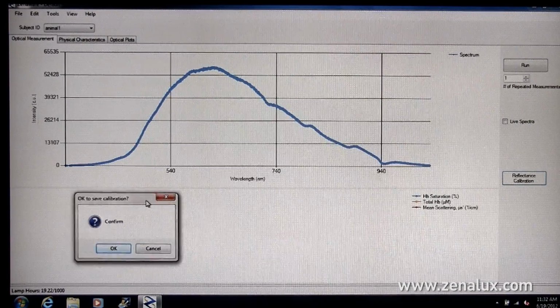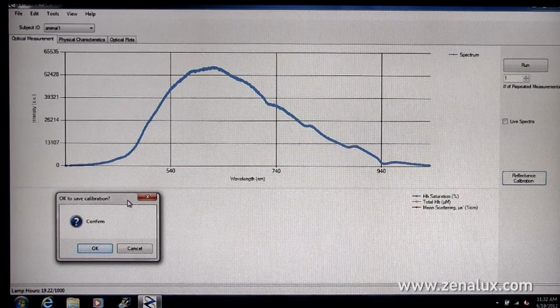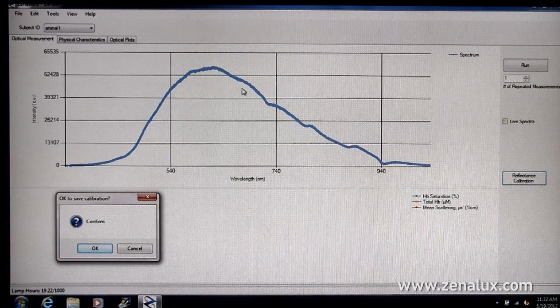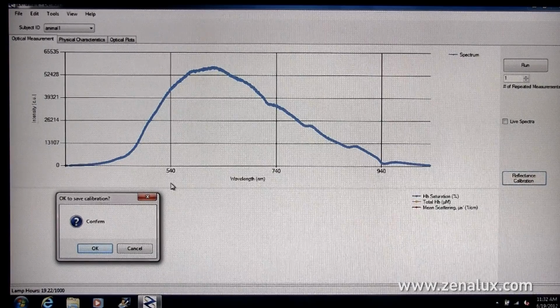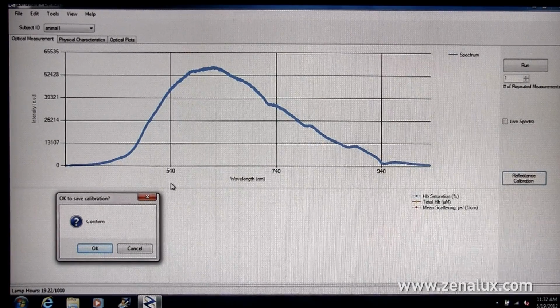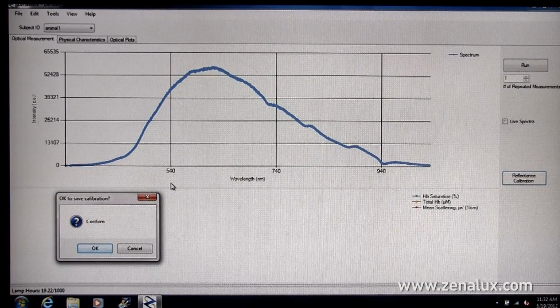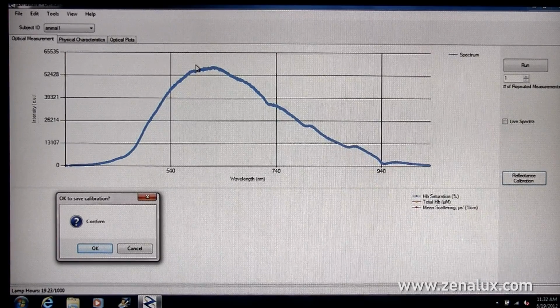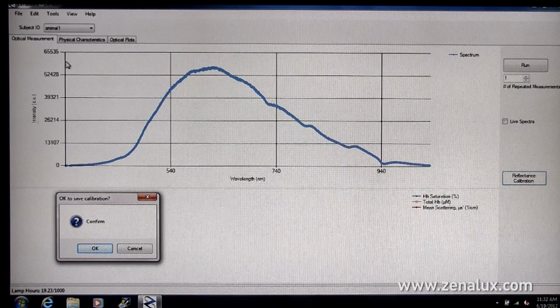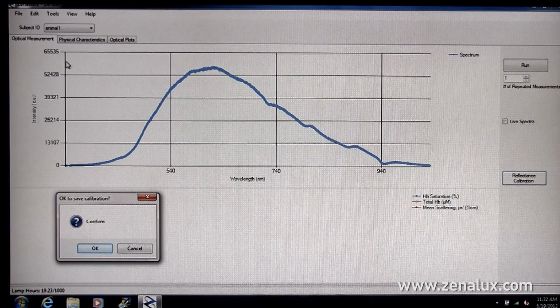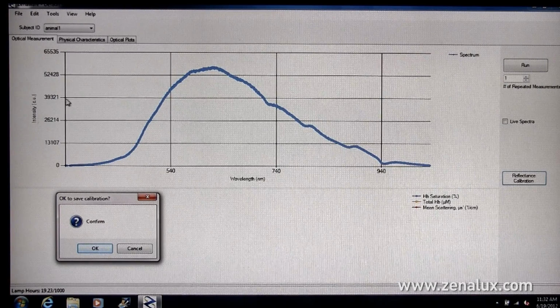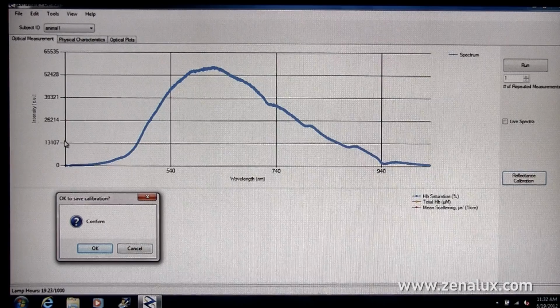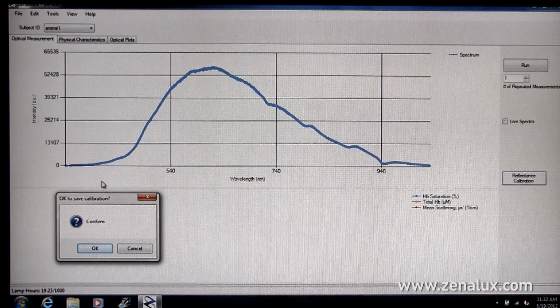What appears is a diffuse reflectance spectrum of our calibration standard. You're looking for two things with your calibration measurement. First, you're looking for good signal. We know that we have good signal if our top peak is below 65,000 counts and above 13,000 counts. This is a great calibration measurement.